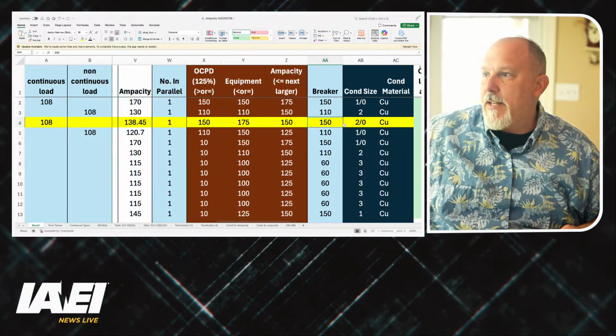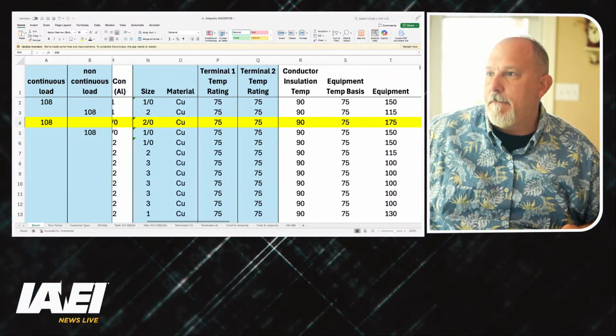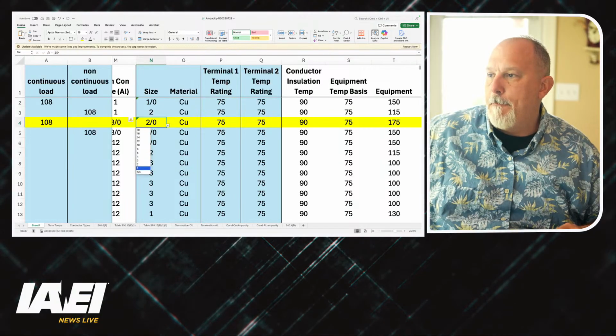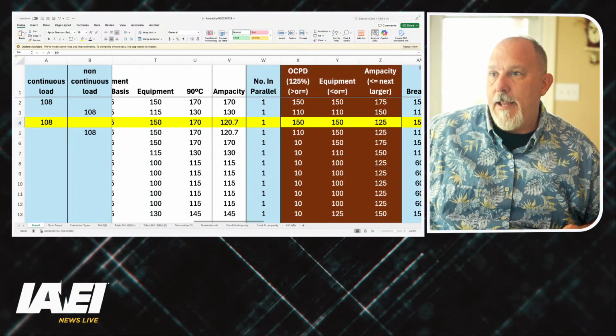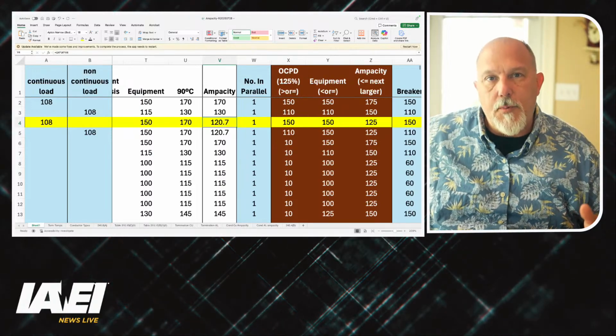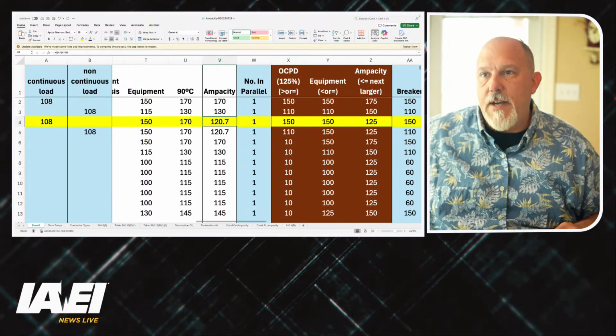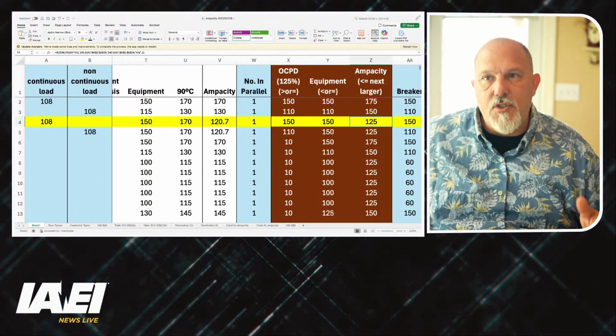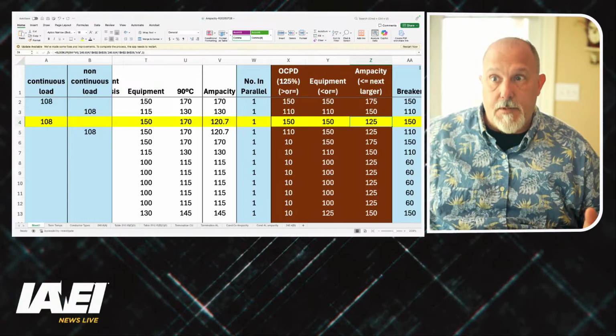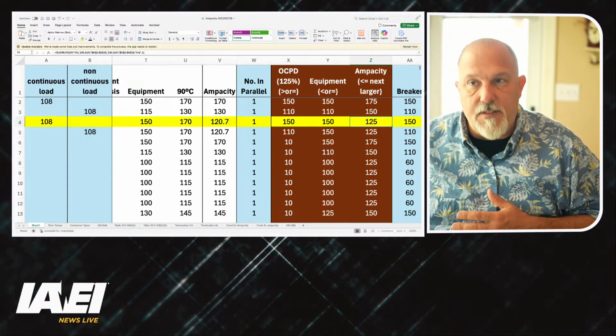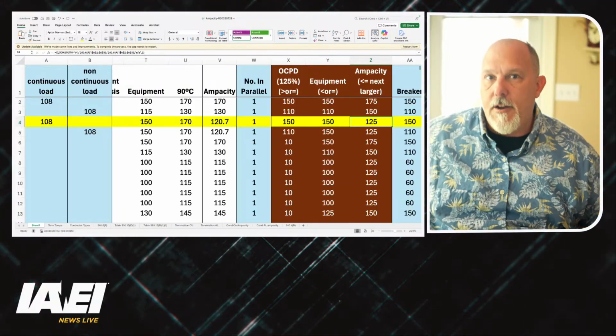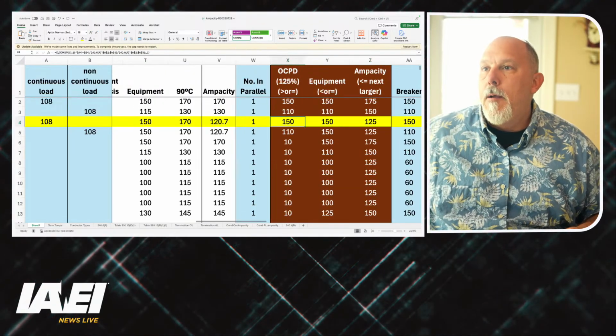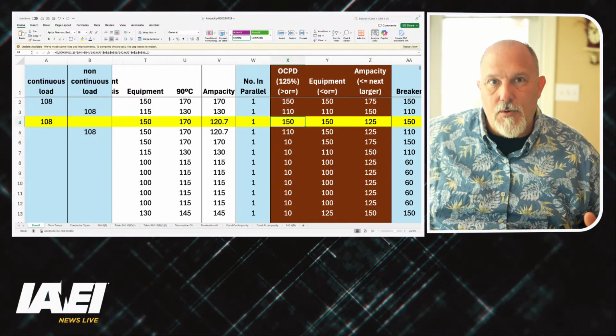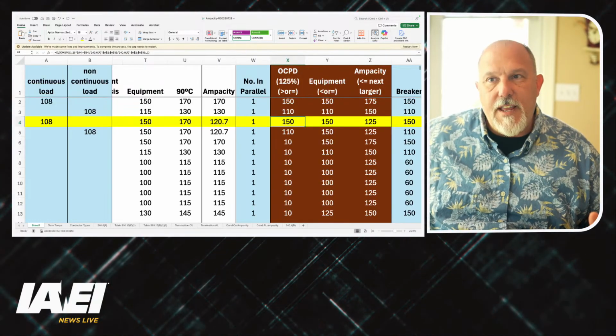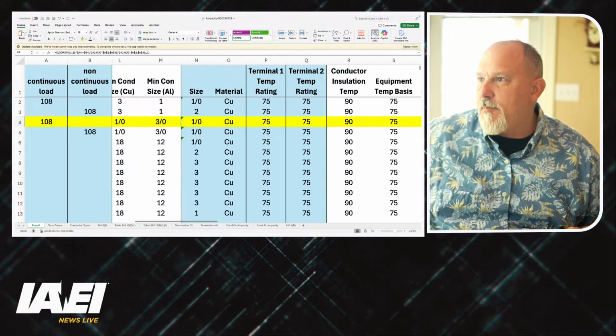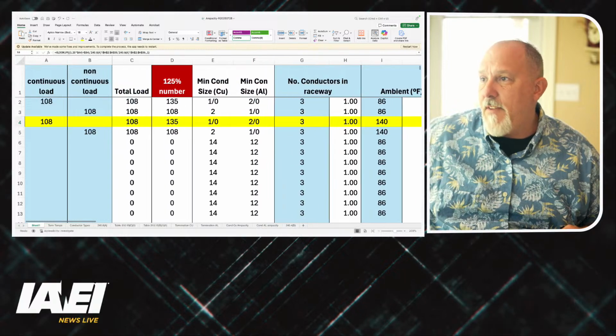because of my overcurrent protective device. Let's go back and do that again. Let's take it back to a 1/0 to explain why. My ampacity of a 1/0 is 120.7. My overcurrent protective device would have to be a maximum of 125 amps. I could be less than 125 amps, but I can't be greater than 125 amps. My 125% rule puts me into a 150 amp breaker.